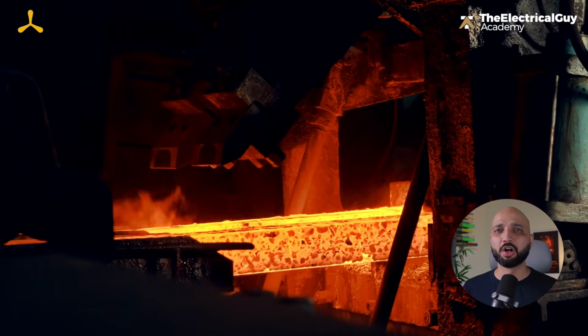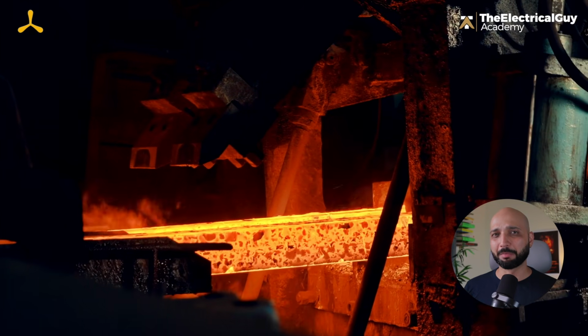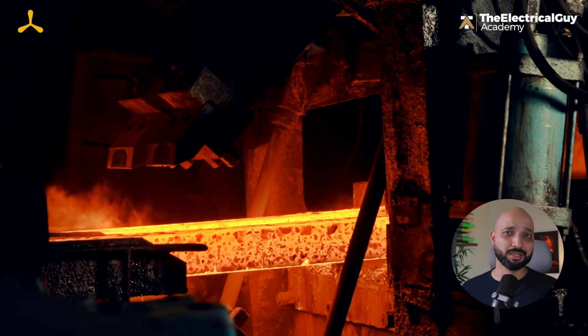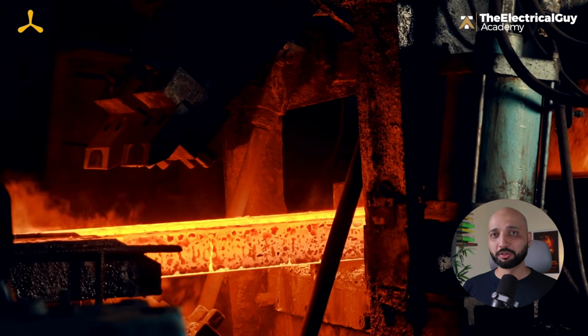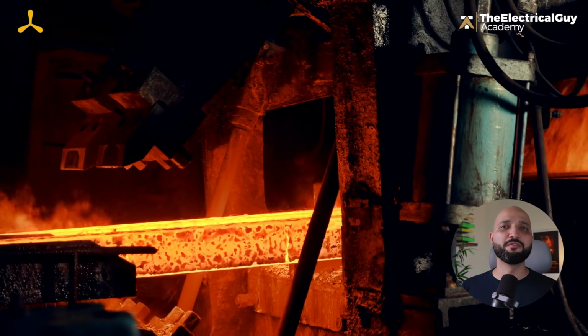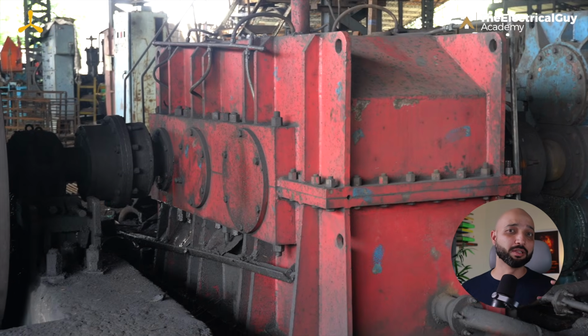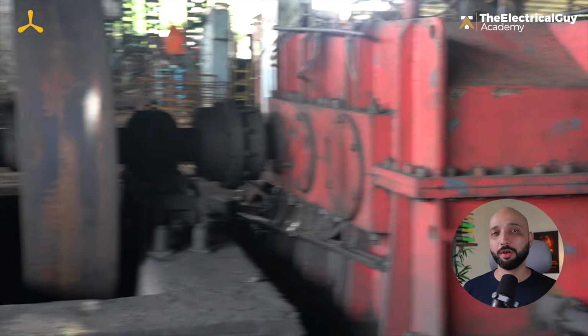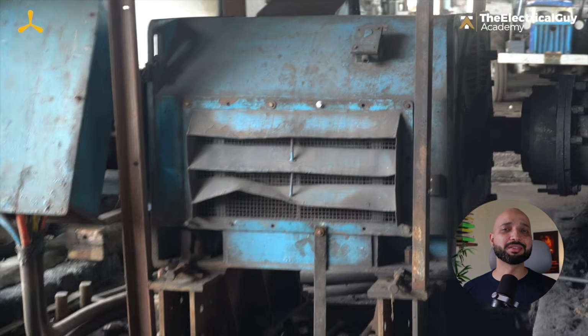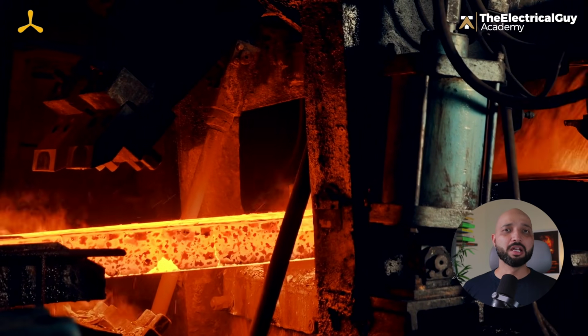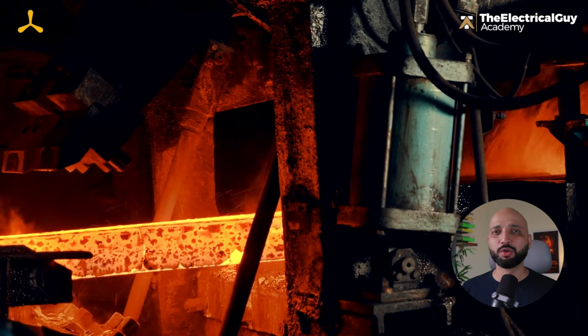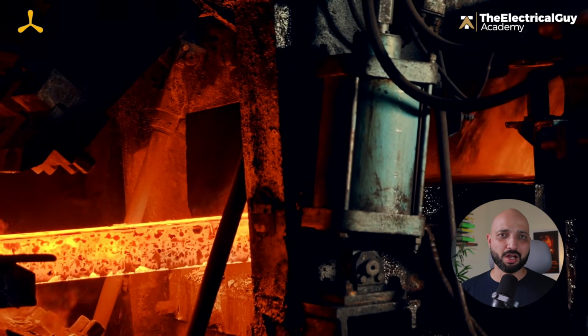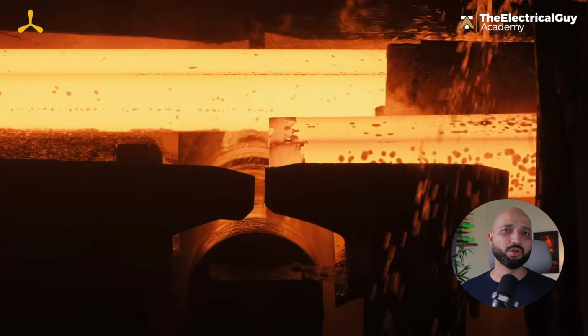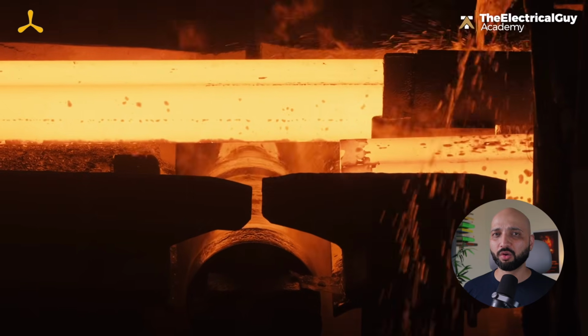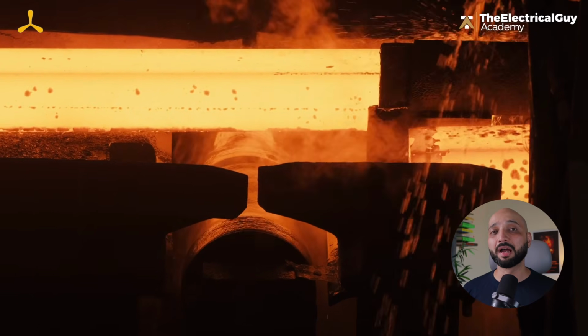In a steel rolling mill, hot steel billets or the slabs are passed through rollers to reduce their thickness or change their shape. During this process, the motor has to deliver a very high torque, especially when the hot steel first enters the roll. This movement creates a sudden impact on the motor and the drive system. That is why normal motors are not suitable for this kind of duty. Rolling mill duty motors are designed to handle frequent starts, heavy overloads, mechanical shocks, and high temperatures.